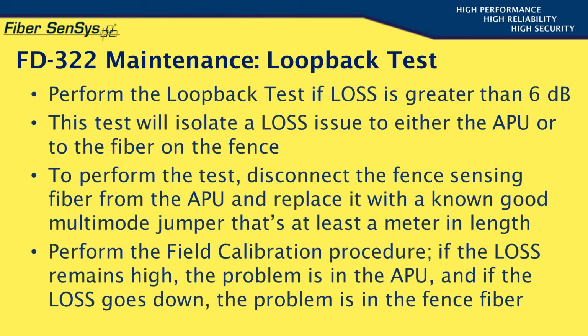If you encounter any zone with more than a 6 dB loss, it can be helpful to perform a loopback test to isolate the problem to either the APU or to the fiber on the fence. You'll need a known good multi-mode optical jumper cable to perform this test. To execute, disconnect the fence-mounted sensing fiber from the APU and replace it with the test jumper. And don't forget to clean and examine the test cable ferrules before connecting the test jumper to the APU.